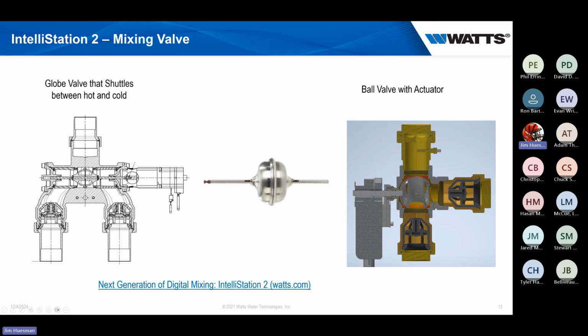I actually have a small video showing this operating, how it works. We're blending more with a shuttle now, where we're able to convert our actuator to physically screw this in to allow more hot, or unscrew it to get more cold. Because they've added such a fine thread, we can really dial in on those temperatures, because 120 is 120 - not 120-ish. We want that to hit directly on the spot.